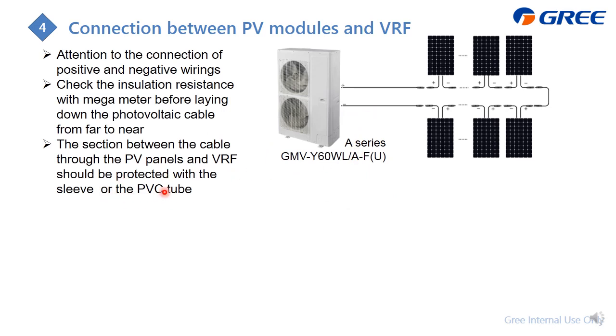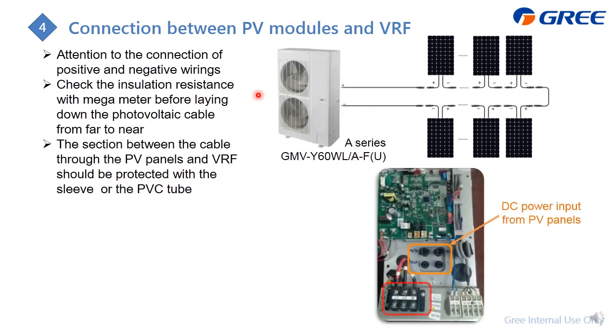And on the outdoor unit, you just open the panels, and here is what you can see. This is connected to the DC power, which is from the PV panels. So you can just plug this MC4 into here. It's okay. And this is for the power supply from the AC power. And this is for the communication wire to the indoor unit and for the centralized control.